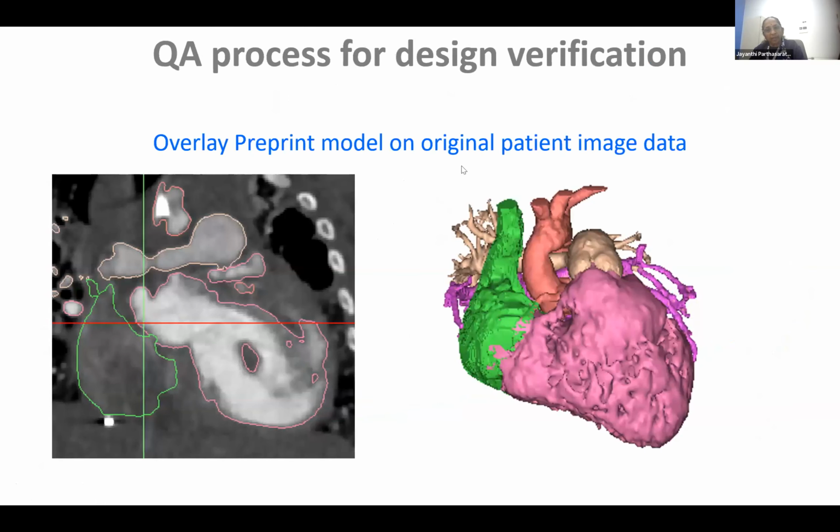Our design verification process goes right from the imaging: the CT happens at 0.5 or 0.625, the MR happens at 1 millimeter, and then you're co-registering that. You're doing independent segmentations, co-registering the STLs, so many things happening. As we saw, we needed some struts and some smoothing.